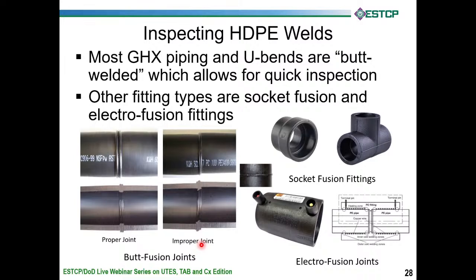It's a great material. That's what gas goes through, unless it's at really high pressure, so they don't have to worry about cathodes and anodes and corrosion. Most of your fiber optics are routed through HDPE. So in the black version you see here, that's typically potable water. HDPE is used for drainage also. But in the context of geothermal heat pump systems, we personally like the double rollback joint that you see on the left here, which is a butt fusion joint right there.